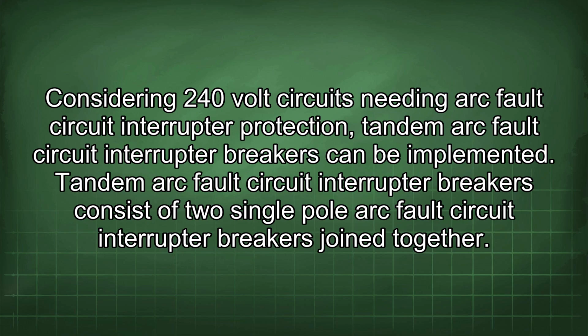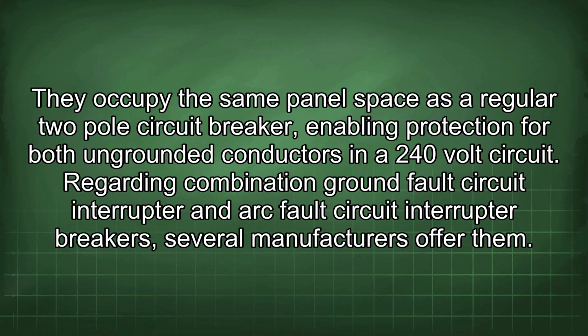Considering 240 volt circuits needing arc fault circuit interrupter protection, tandem arc fault circuit interrupter breakers can be implemented. Tandem arc fault circuit interrupter breakers consist of two single-pole arc fault circuit interrupter breakers joined together. They occupy the same panel space as a regular two-pole circuit breaker, enabling protection for both ungrounded conductors in a 240 volt circuit.